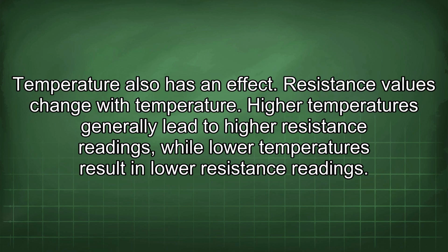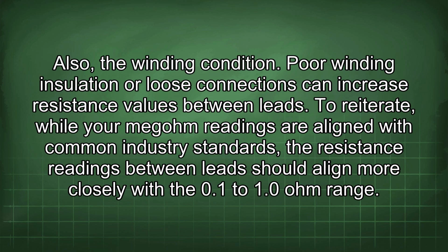Temperature also has an effect. Resistance values change with temperature. Higher temperatures generally lead to higher resistance readings, while lower temperatures result in lower resistance readings. Also, the winding condition. Poor winding insulation or loose connections can increase resistance values between leads.